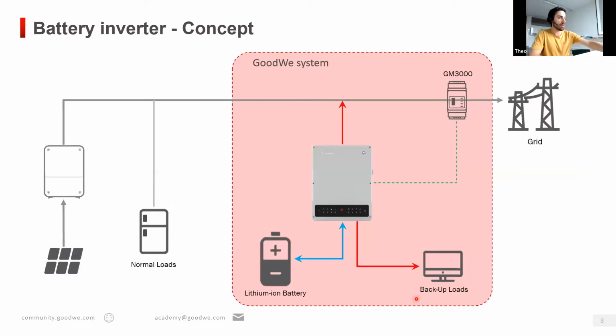If we now look at the battery inverter, this is the other type of storage inverter that we offer. And this is like a retrofit solution. So shortly to explain the concept here, if you think away this red box here, so first off, we have what we have here on the right side. So here we have an inverter. This could be a GoodWe inverter. It could also be a third-party inverter. You have the PV connected and you connect it to the AC line. And here are your loads as well, also connected to the AC line. So this is your already set system.